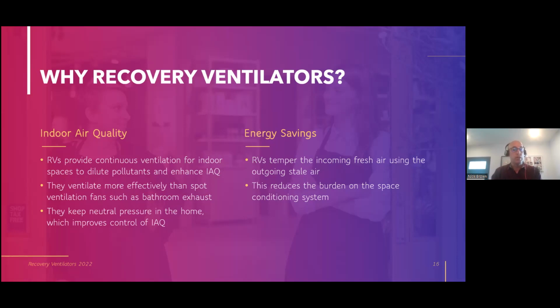Then we've got the energy savings perspective. This is the part the energy code cares about, but it's just one of 4 categories of benefits that I'm presenting to you today. And they create energy savings by tempering the incoming fresh air that we're required by code to bring in using the outgoing stale air heat. This reduces the burden on our space conditioning system. We'll talk more about how.